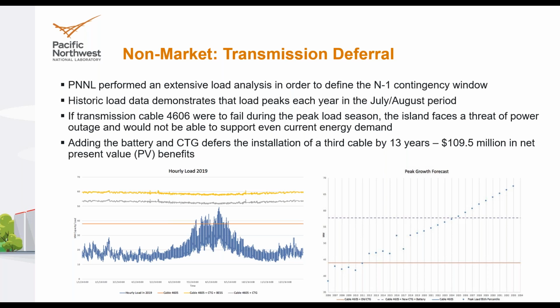You can see the lines there that show combinations: for just one cable, or the cable plus the combustion turbine generator plus the battery storage system, or the cable plus the combustion turbine generator. This is showing that if those peak hours exceed the orange horizontal line, you're in the N-1 contingency window. If you exceed the gray line, you're in it even with consideration of the combustion turbine generator. The orange squiggly line on top effectively shows you the entire system.